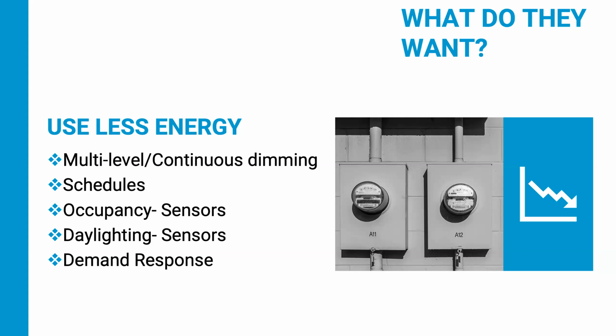Another thing is reduction of light within occupant leaving—some codes say 15 minutes, others 20, so it's gotten tougher. Last year it was 30 and 20 for the 2016 requirements. Things are getting a little tighter, and it's hard to do now just with a luminaire-based control—you're going to need something networked so you can have zones and handle those different timeout requirements.